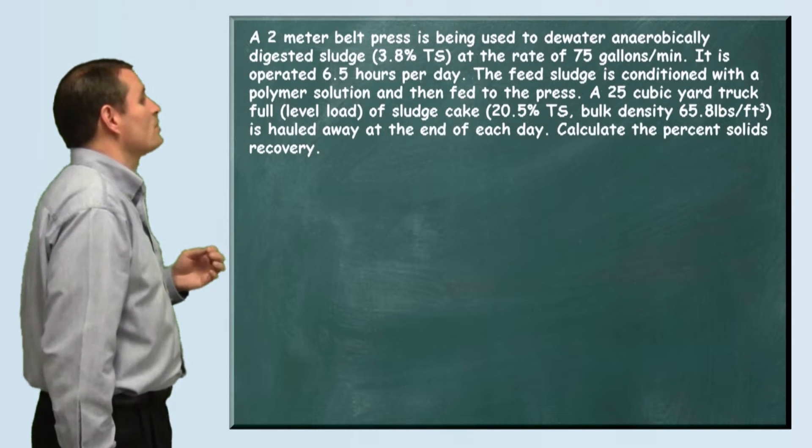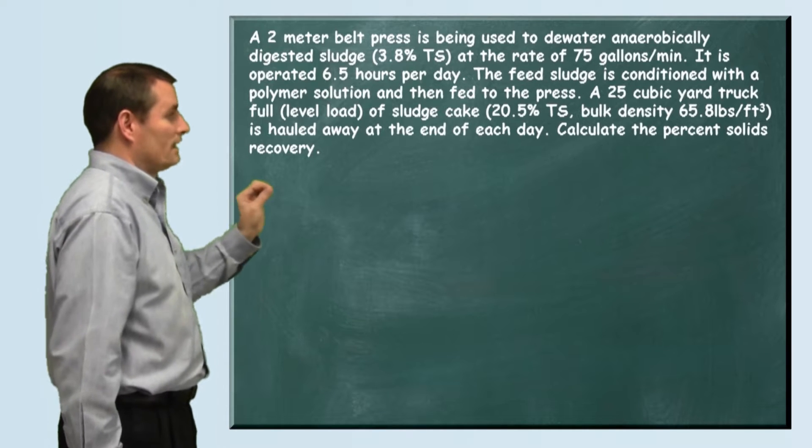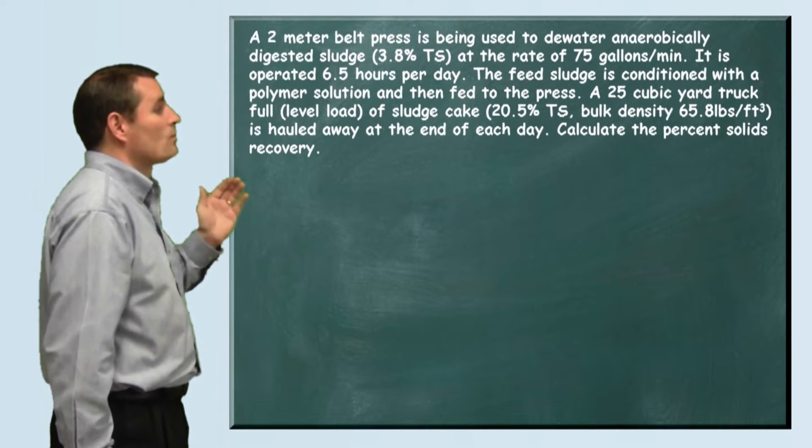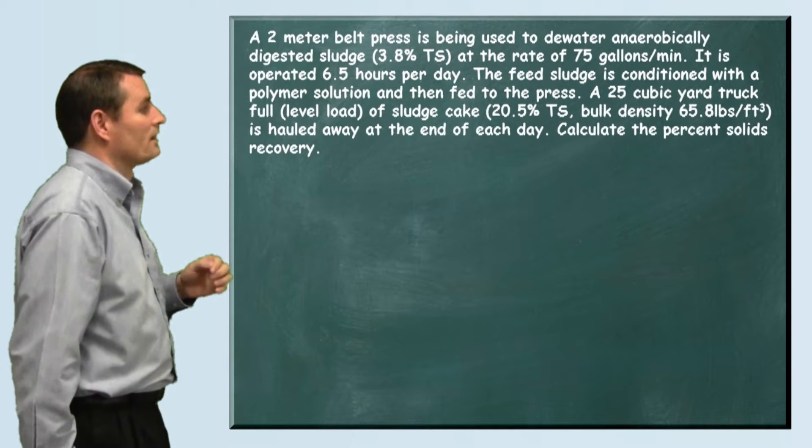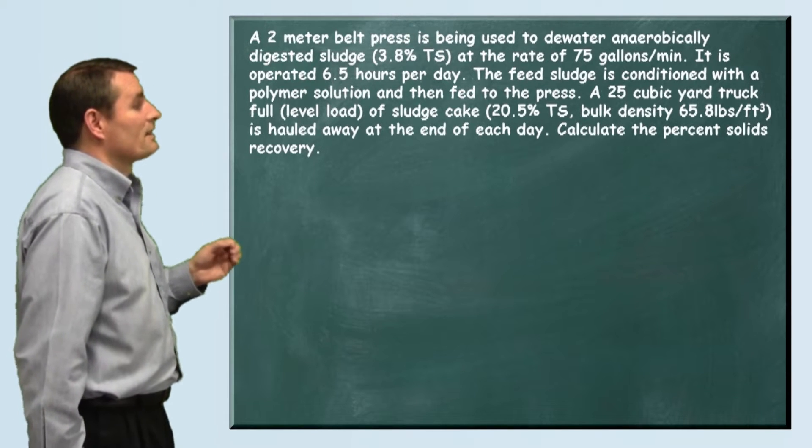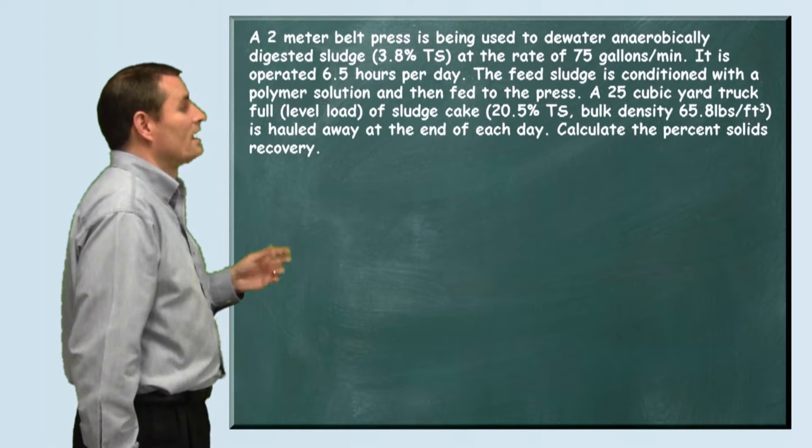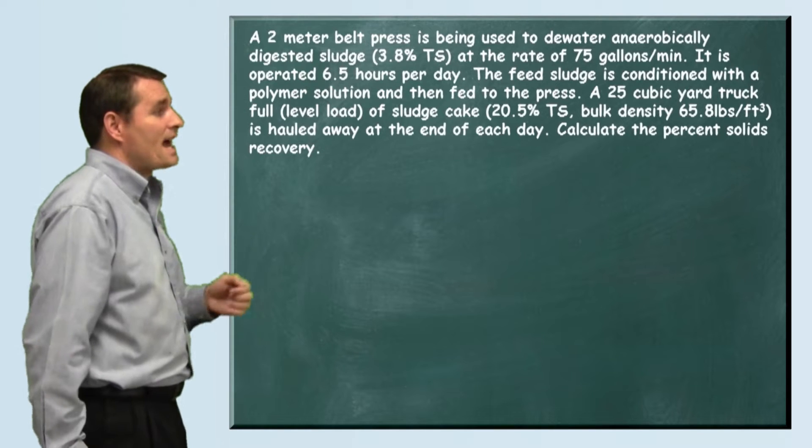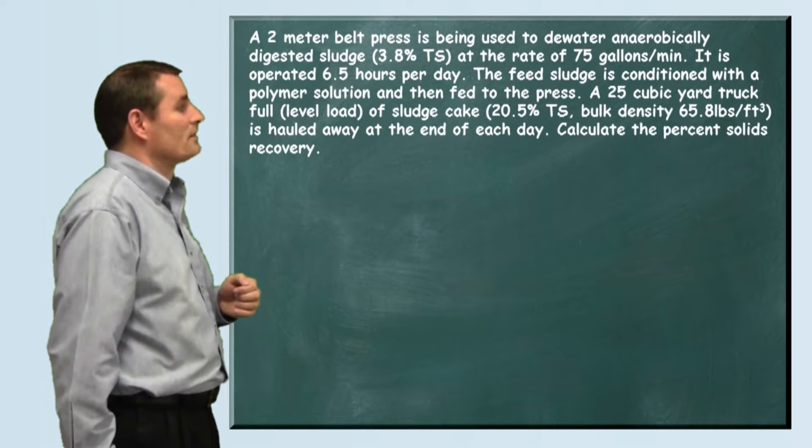A 25 cubic yard truck full, a level load of sludge cake with 20.5 percent total solids and a bulk density of 65.8 pounds per cubic foot, is hauled away at the end of each day. They want us to calculate the percent solids recovery.